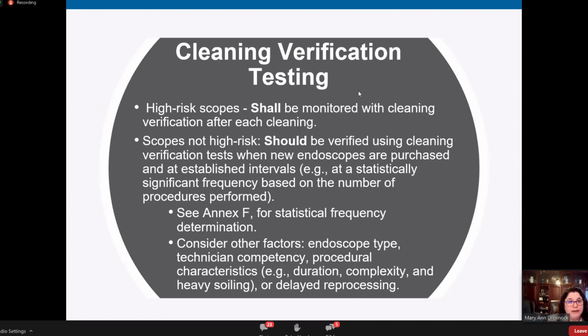So you're more likely, if it passes a cleaning verification test, to go on and actually achieve high-level disinfection or sterilization. We had it as a recommendation in the last ST91 to periodically monitor, and then we meant weekly, preferably daily is what we said. So we've really amped that up now. For the high-risk scopes it's a shall, as Garland said. So that is something you would have to do per the standard every time for every high-risk scope. And for non-high-risk, as he said, you should verify those on a pre-established interval. And we have an annex there to help you determine what that frequency is.